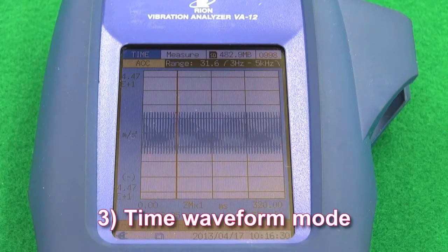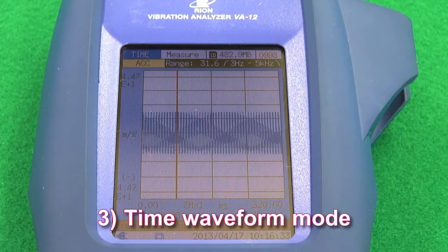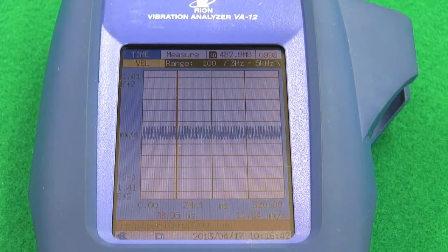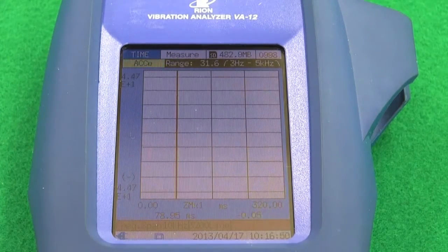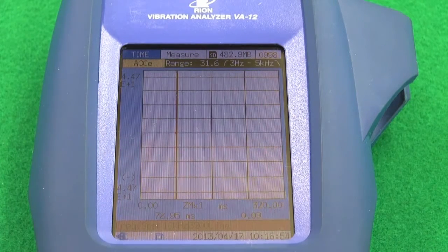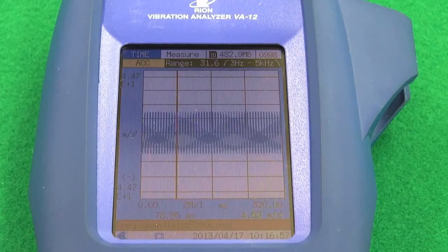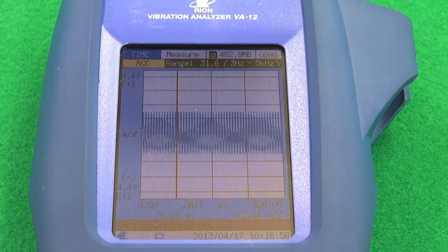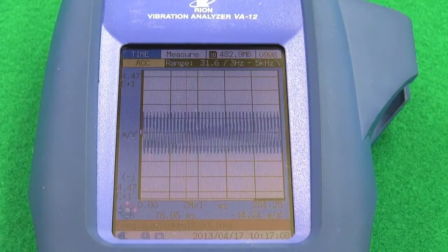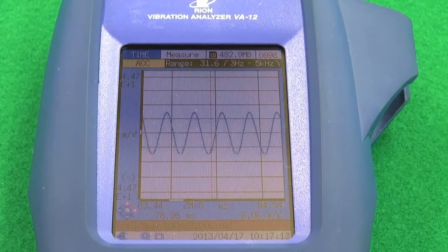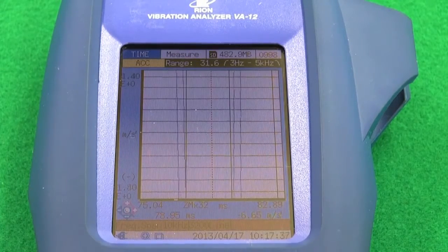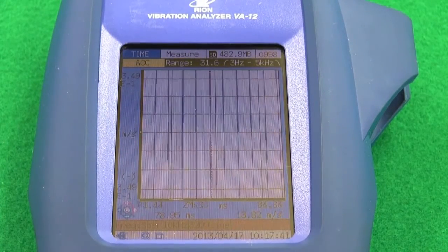Feature three: Time waveform mode. In time waveform mode, acceleration waveforms, velocity, displacement, and acceleration envelope curves can be displayed using up to 8,192 samples. The time waveform display, like an oscilloscope, has a time axis which can be magnified up to 32 times and a magnitude axis that can be magnified up to 16,384 times.